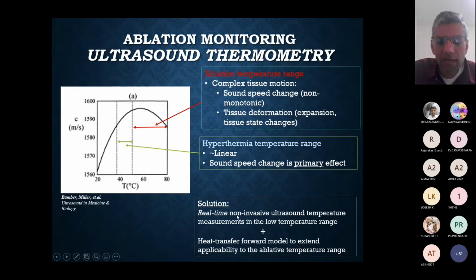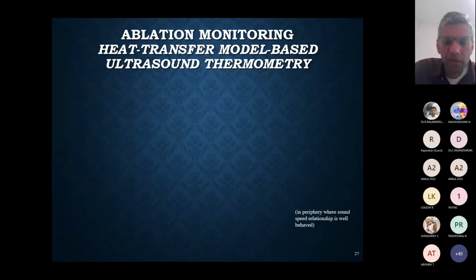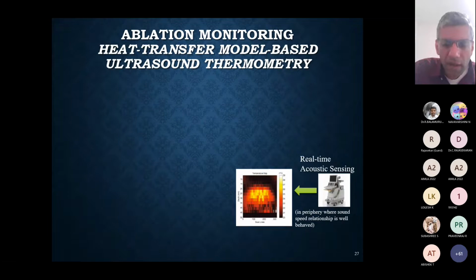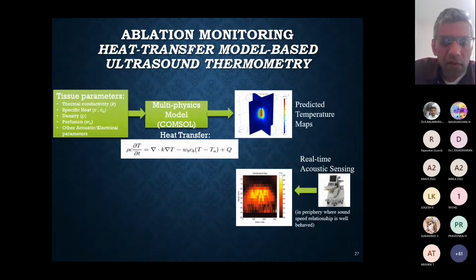What we did is come up with a hybrid approach. You do real-time temperature measurements in the low temperature range, and combine that with a model, which can be done using machine learning. It also uses a physical model — a heat transfer model — to expand the temperature estimation into the ablative temperature range. I won't go into too much detail, but at a high level, we are acquiring temperature estimates using the ultrasound system in real time.